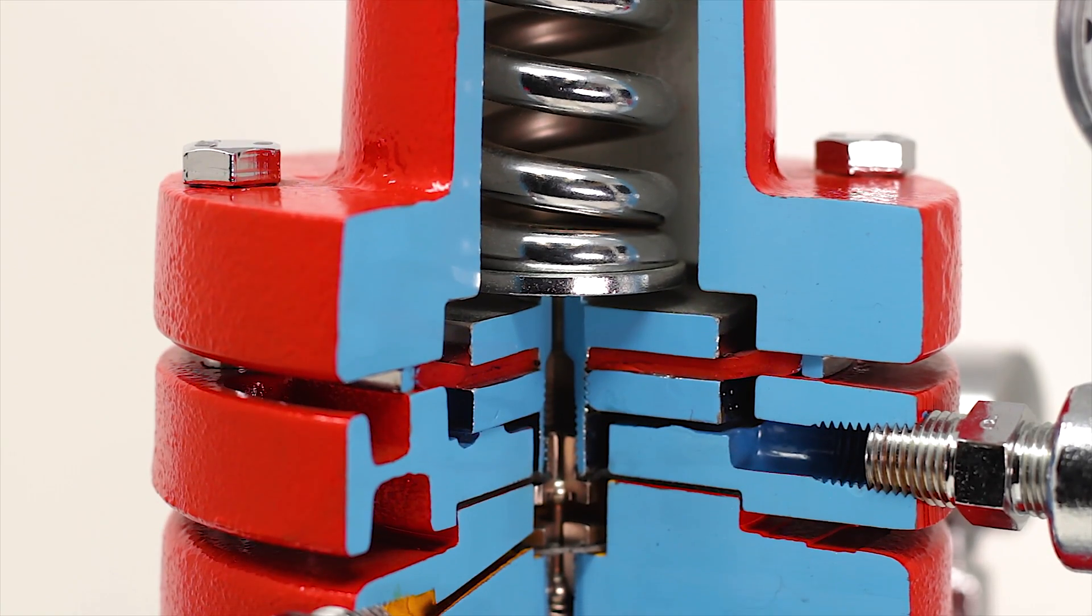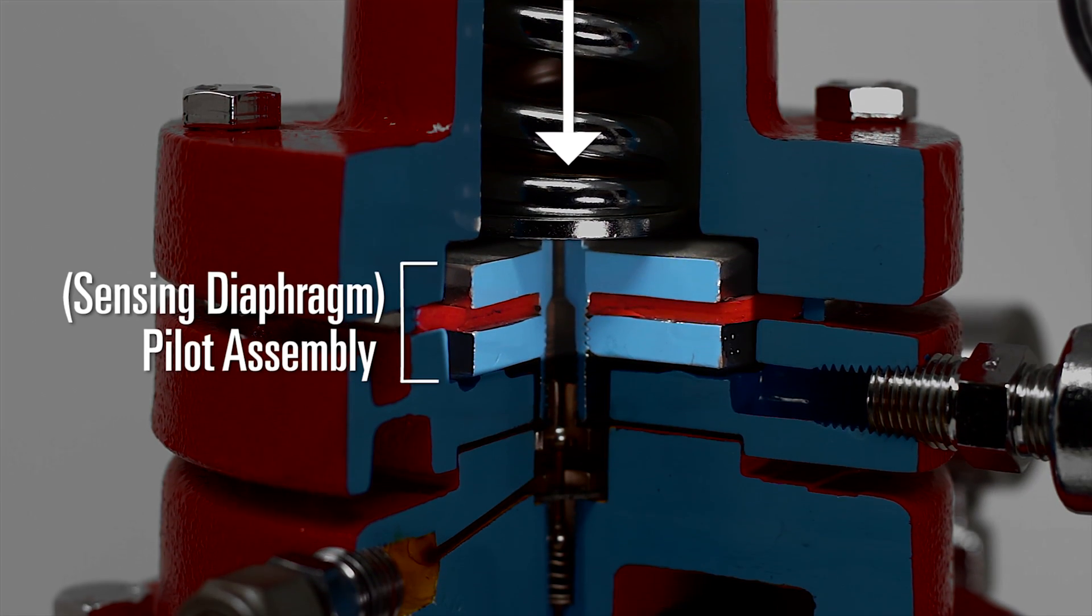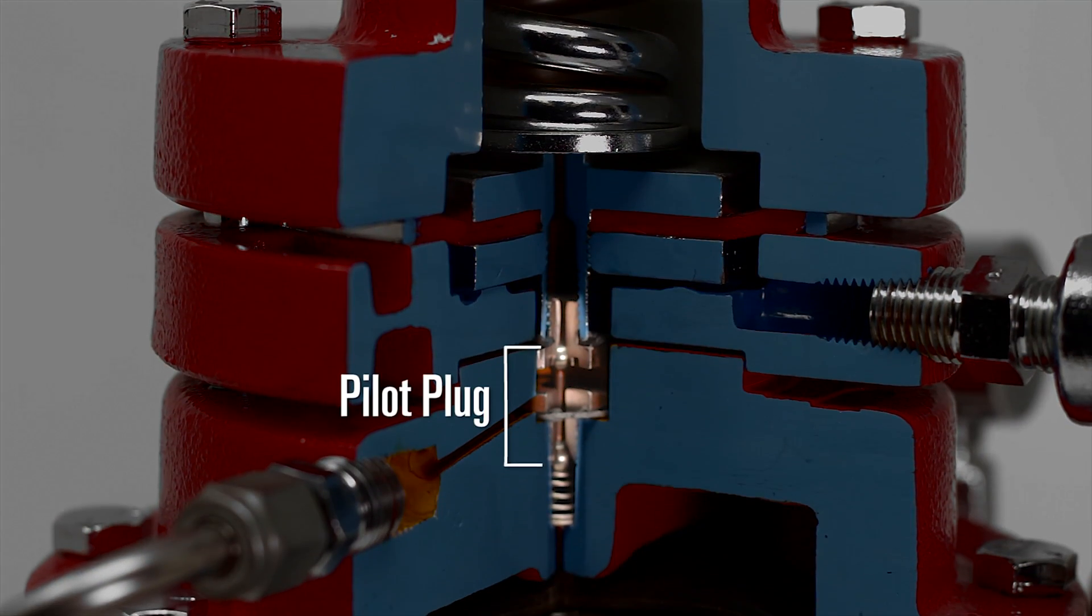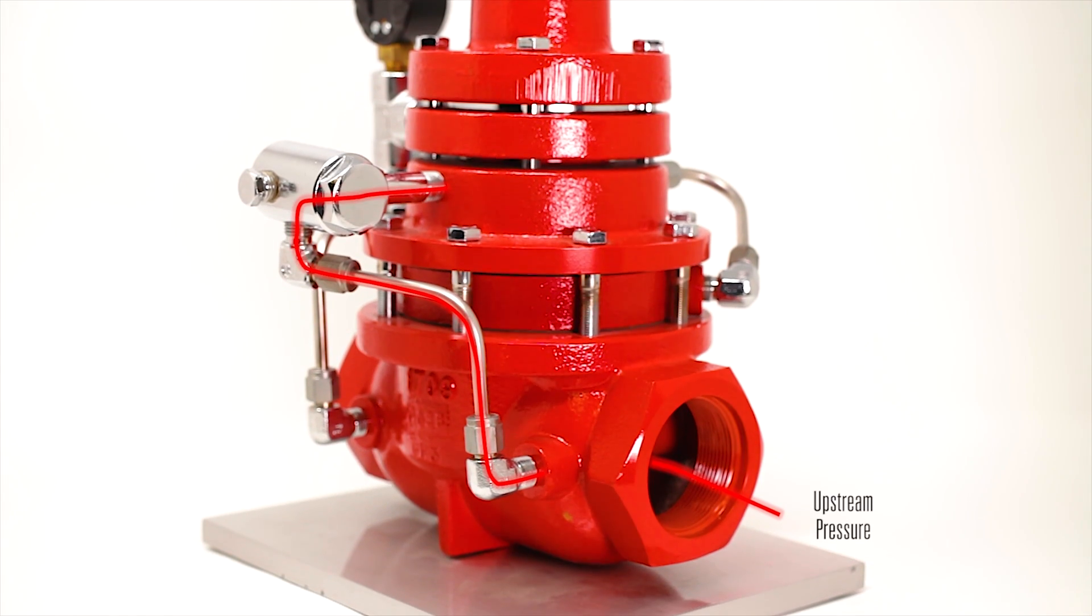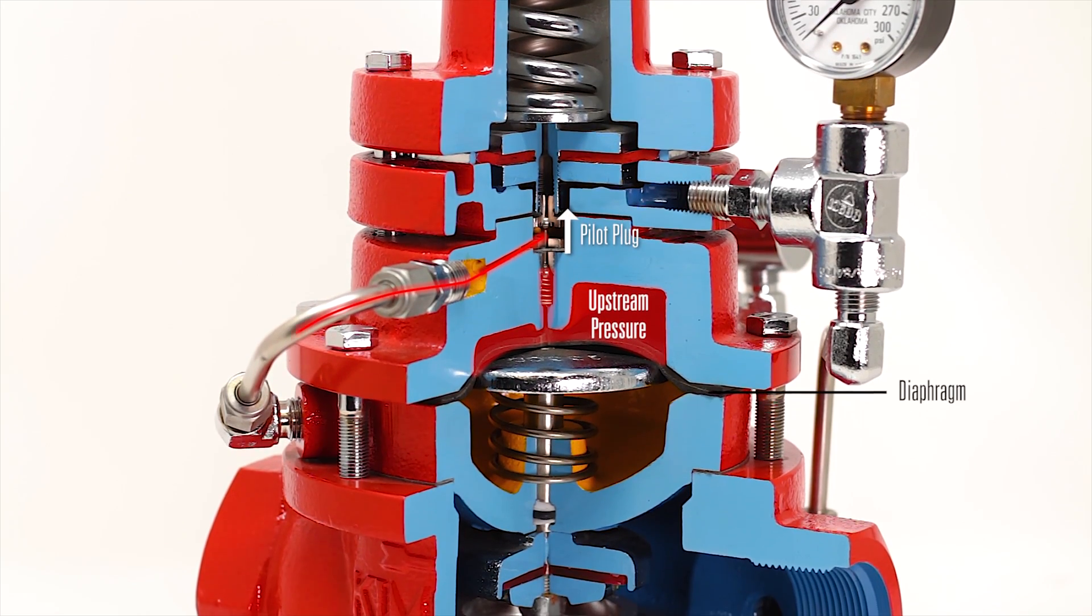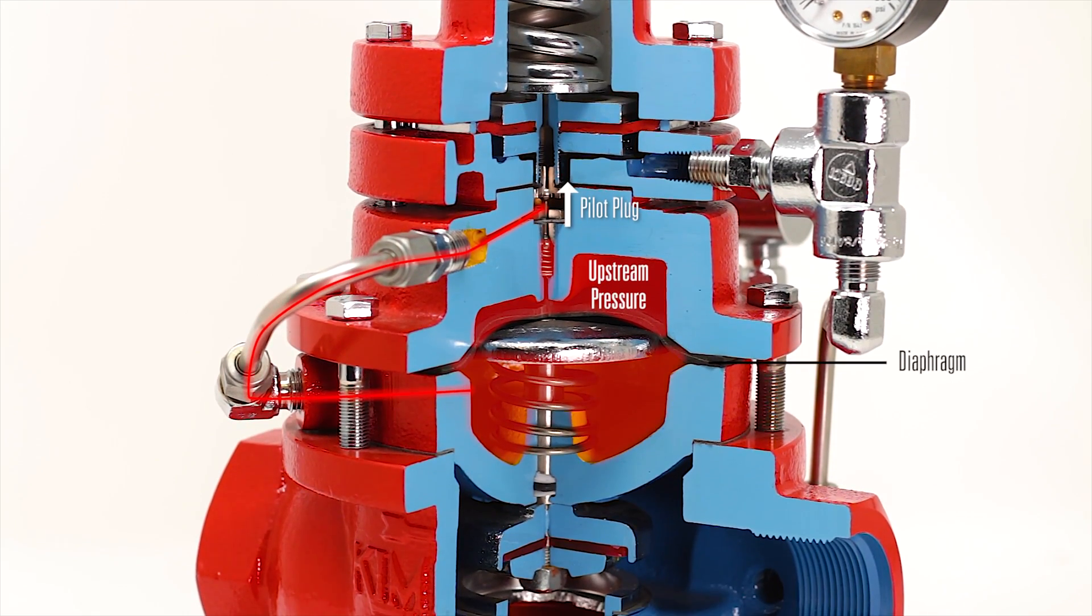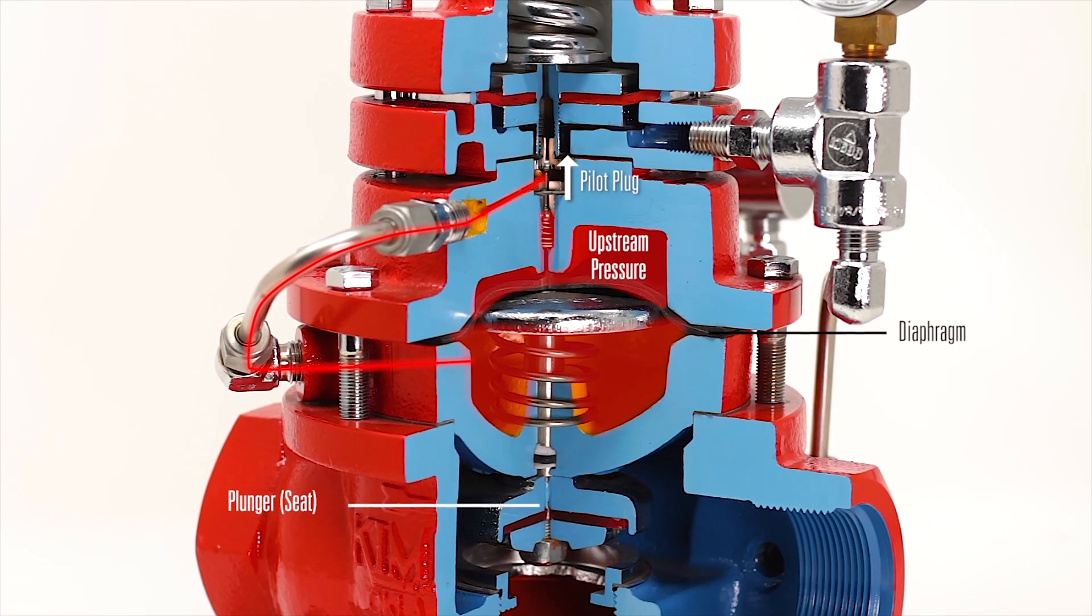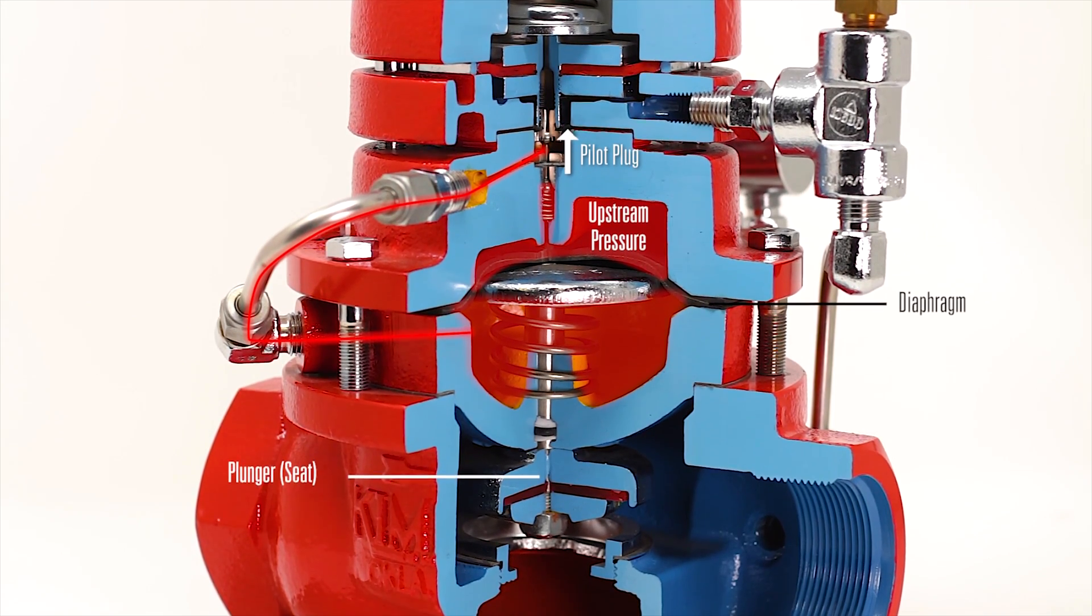The spring pushes down on the sensing diaphragm assembly which positions the pilot plug. The pilot plug then allows gas from upstream to flow under the motor valve diaphragm. The pressure is controlled under this diaphragm to position the plunger to any changes in flowing conditions.